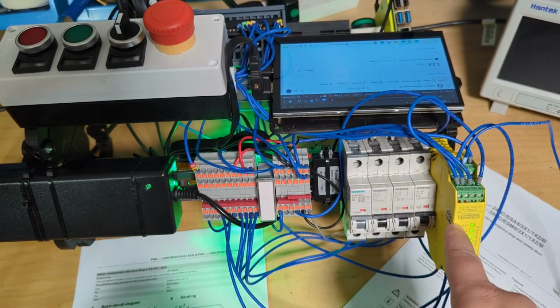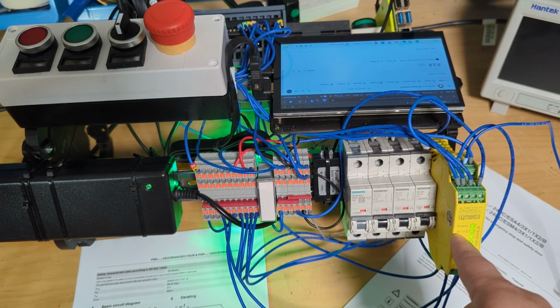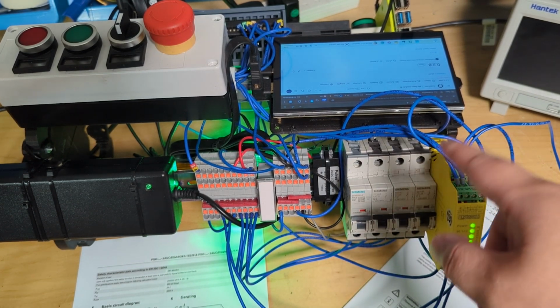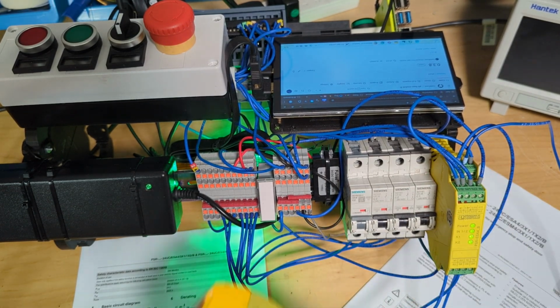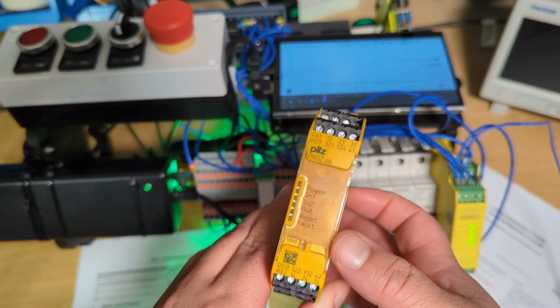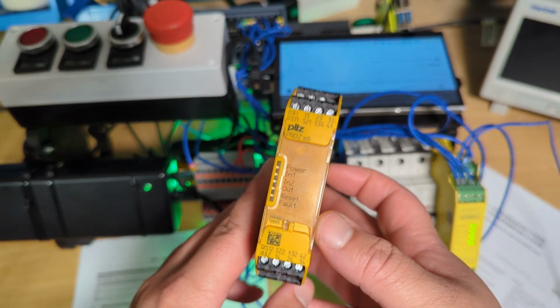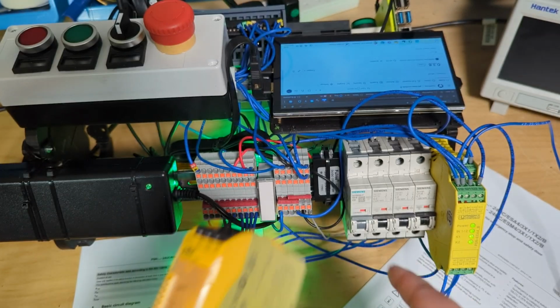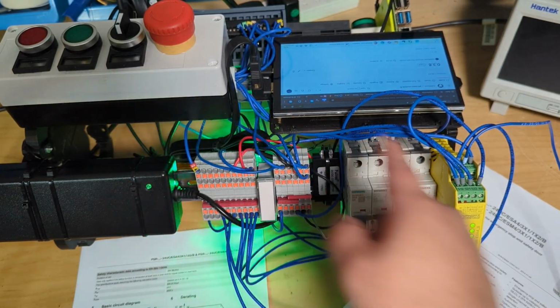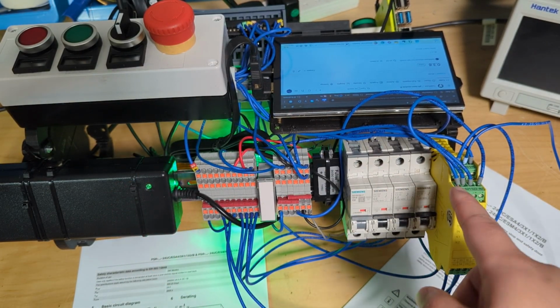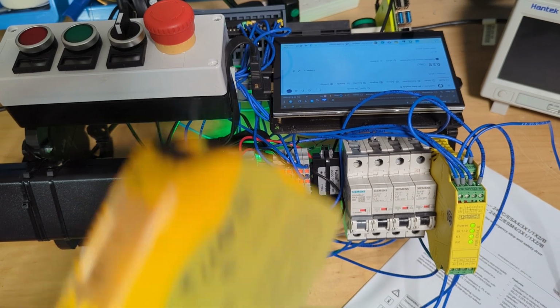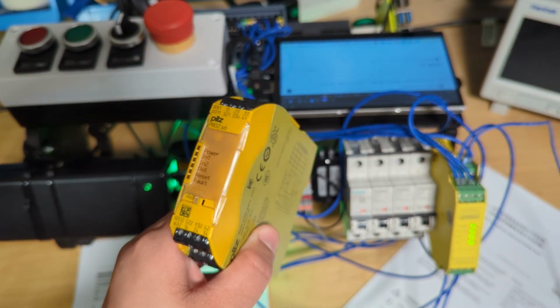This Phoenix Contact one can be used in single channel mode or dual channel mode, and it can be used for e-stops or safety doors. This is a different one, which is only used in dual channel mode, so you can't put one input in. So if my e-stop only had one normally closed signal, this relay would be fine, but this one wouldn't. So you need to know the difference.